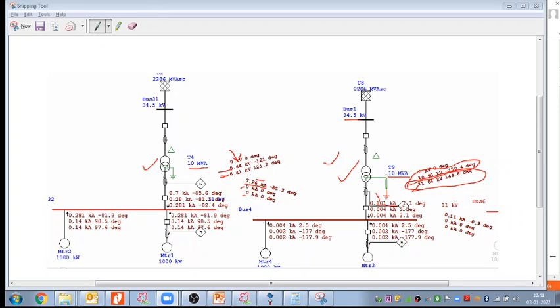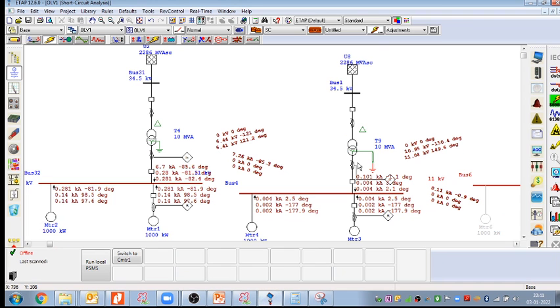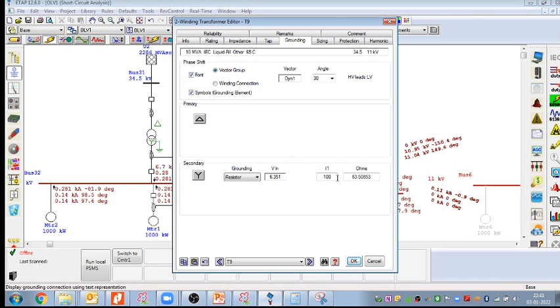Here I explained two important concepts. Concept number one is how to select the current, how much current we want to allow to flow. Like in ETAP also we have to put this current, then it will give the ohm, right? So to decide this current, there are two concepts. Concept number one, we can discuss with the vendor how much current their core can withstand, and based on that we take this current, keeping it less than their core withstand capacity. Or if you cannot get this information from the vendor, then take at most the full load current of the generator or the transformer, not more than this.